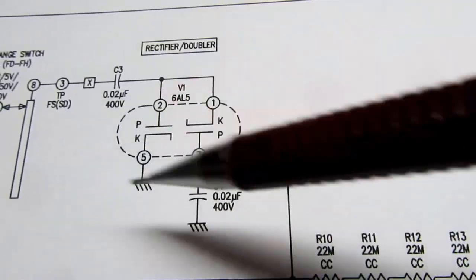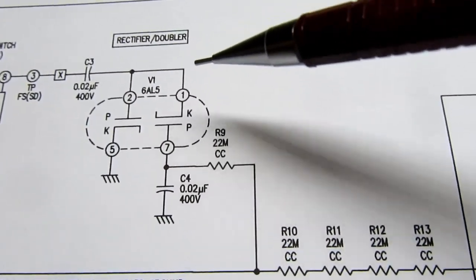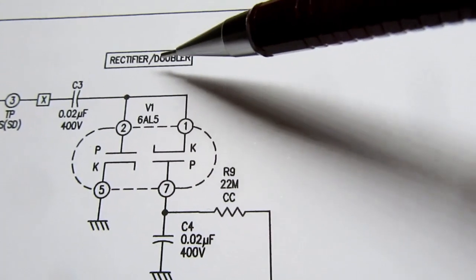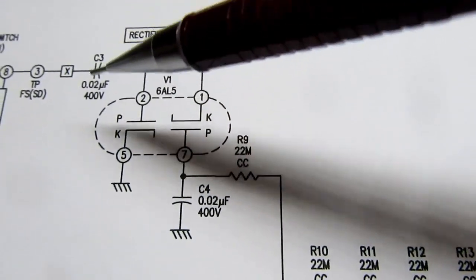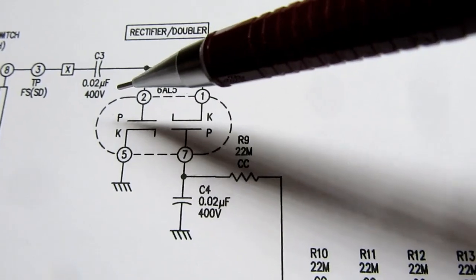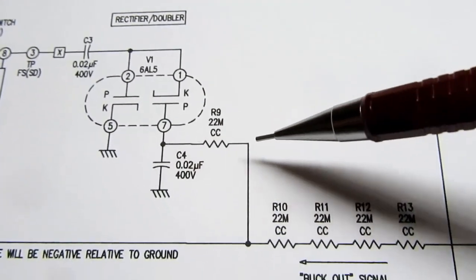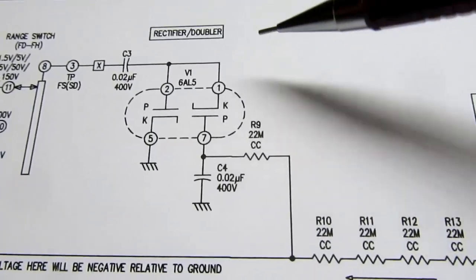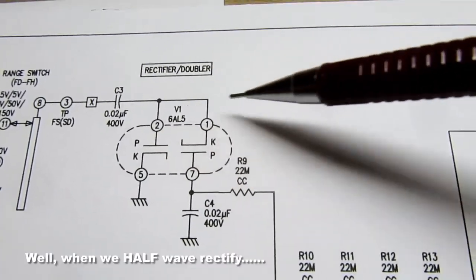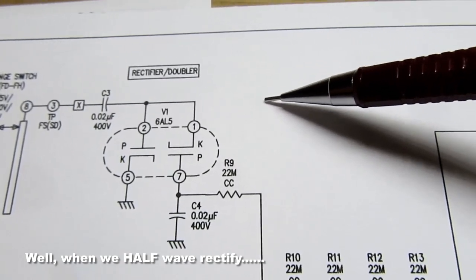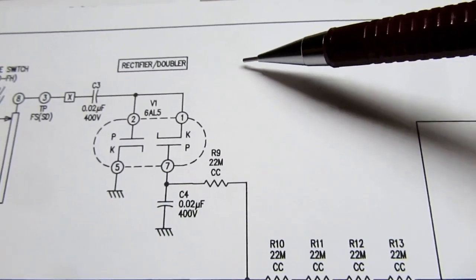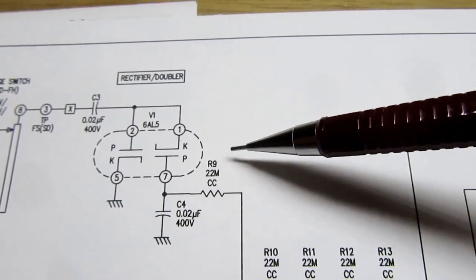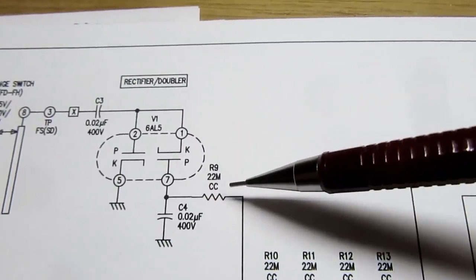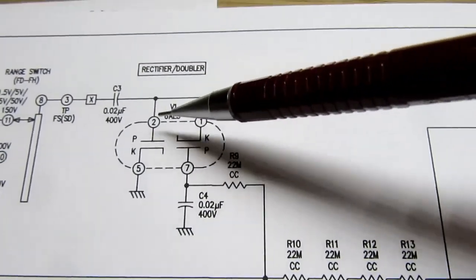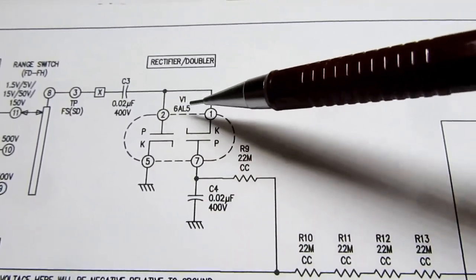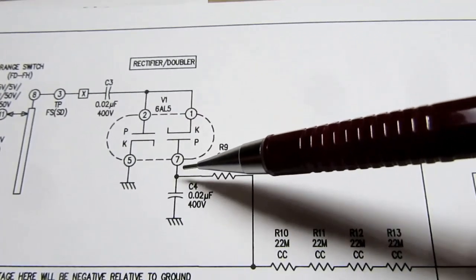I'm going to talk about how this works separately, but for now we'll just regard it as a rectifier and voltage doubler circuit. So it's going to rectify it, and then it's going to take the rectified voltage and double it, and that's what's going to come out of here. The reason we're doing that, in a nutshell, is that when we rectify something, we take only half the waveform. But we're trying to measure from the top to the bottom of the waveform, in other words, peak to peak. So the way we do that is we measure half the voltage by virtue of the rectifier, and then double it to get the peak to peak voltage.